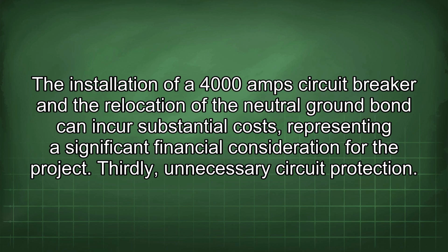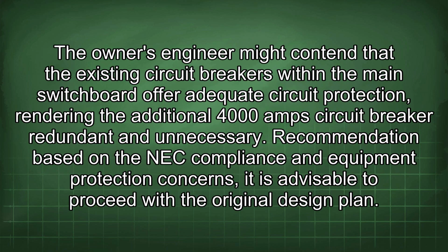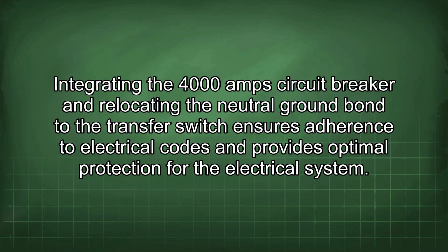Thirdly, unnecessary circuit protection. The owner's engineer might contend that the existing circuit breakers within the main switchboard offer adequate circuit protection, rendering the additional 4000 amp circuit breaker redundant and unnecessary. Recommendation. Based on the NEC compliance and equipment protection concerns, it is advisable to proceed with the original design plan. Integrating the 4000 amp circuit breaker and relocating the neutral ground bond to the transfer switch ensures adherence to electrical codes and provides optimal protection for the electrical system.